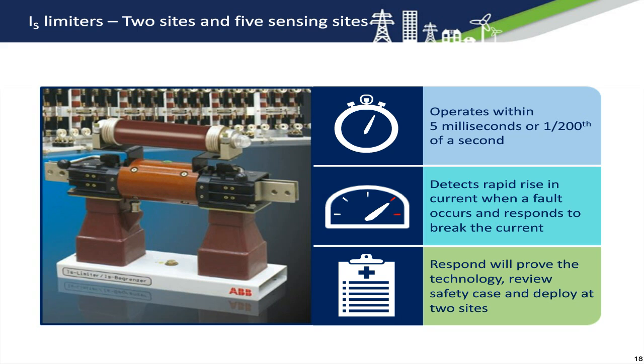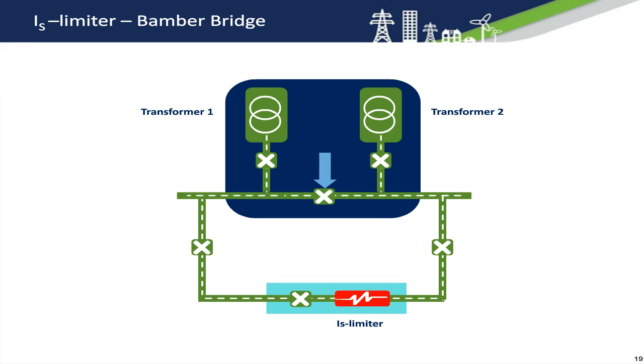We have 2 sites where we are trialling the IS limiter. The first is at Bamber Bridge in Preston. At this site we have the substation busbar section open, and the IS limiter is acting as a closed busbar section breaker. If the fault level is exceeded for any of the circuit breakers at the substation, the fault level assessment tool will enable the IS limiter. If a fault then occurs, the IS limiter will operate in 5 milliseconds and effectively open the busbar section at the substation, which halves the fault level the circuit breakers will see, therefore operating safely.